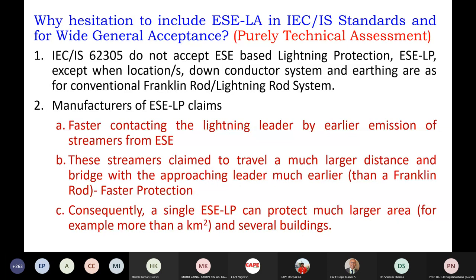IEC 62305 does not accept ESE-based lightning protection, except when the locations, down conductor systems, and earthings are strictly as per conventional Franklin rod lightning rod systems. The number of down conductors and the earthing system must be the same as for Franklin rods. Only then is it acceptable. That is a very, very good statement.